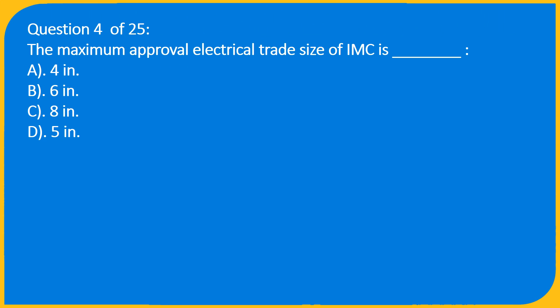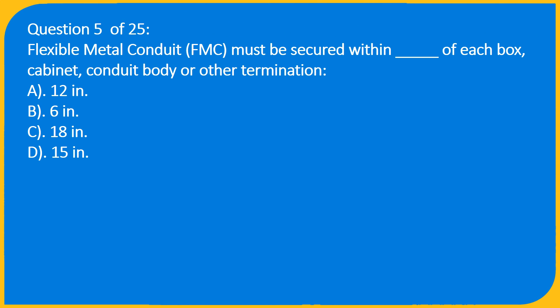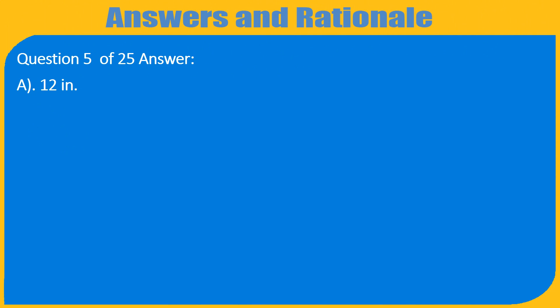Question 5 of 25: Flexible metal conduit (FMC) must be secured within how many inches of each box, cabinet, conduit body, or other termination? A. 12 inches, B. 6 inches, C. 18 inches, D. 15 inches. Answer: A. 12 inches.